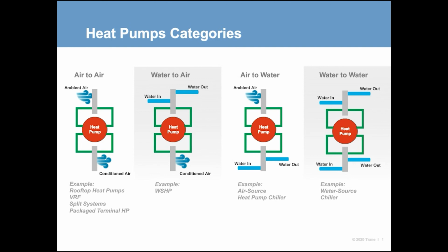The second one there, water to air: the classic example is water source heat pumps. Those have been around for a really long time. But water source heat pumps by themselves are not all electric for the building. If you think about a water source heat pump system, there's also a condensing loop, or a common loop, that goes to all the heat pumps. On that loop, there's usually a cooling tower and a boiler. That boiler is there to condition or temper that loop during the middle of winter. What we're seeing as a great potential retrofit opportunity is this: if you have a water source heat pump system and you're looking to electrify, you can go to an air to water heat pump, the next category, to either offload that boiler or totally replace it.